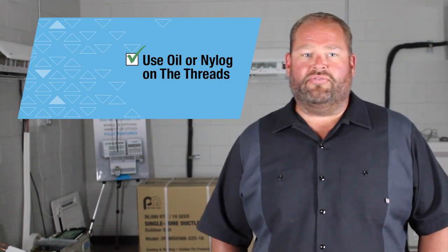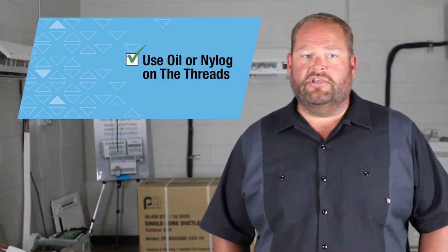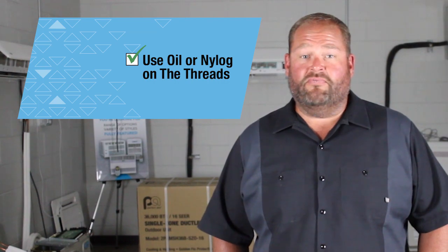Use oil or Nylog on the threads and torque nuts to the proper specified value — see the installation and operation manual for those values. This is a very important step. If you over or under tighten the nut, you will have a leak guaranteed.